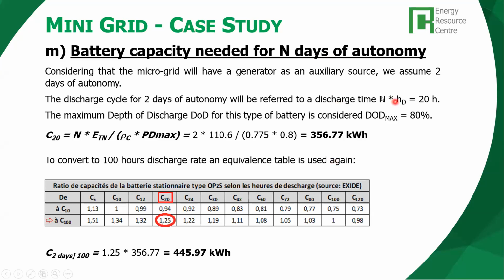And then the discharge time with 2 days of autonomy increases to 20 hours of discharge, a complete charge and discharge cycle for our batteries. Because we have the genset and we have a larger, longer daily cycle of 20 hours instead of 10, we can consider a maximum depth of discharge, but this is really a maximum. We can push these batteries down to discharge them up to 80%, but that's really a maximum. If we consider the 50% that we said before, then the sizing of the battery will be bigger. So bigger batteries and more expensive. So this is really pushing to the limit of reliable performance of the batteries.